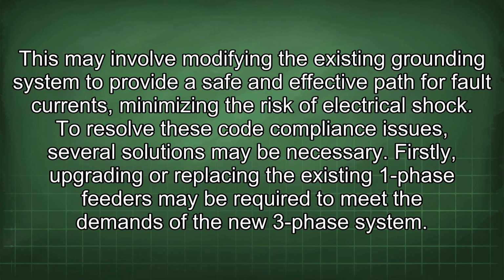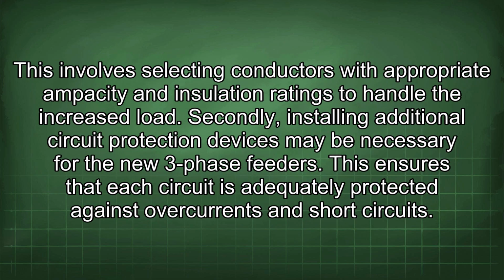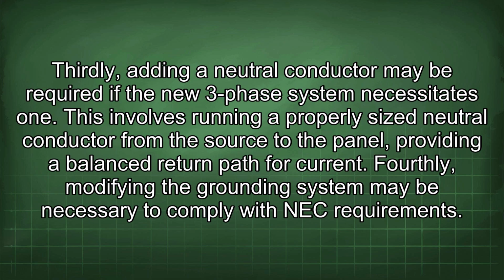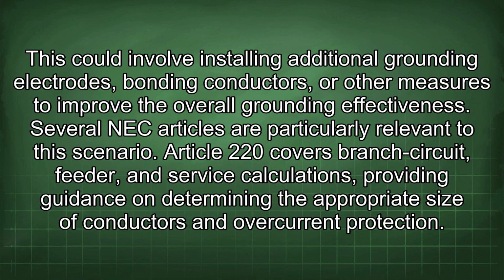Firstly, upgrading or replacing the existing one-phase feeders may be required to meet the demands of the new three-phase system. This involves selecting conductors with appropriate ampacity and insulation ratings to handle the increased load. Secondly, installing additional circuit protection devices may be necessary for the new three-phase feeders. This ensures that each circuit is adequately protected against overcurrents and short circuits. Thirdly, adding a neutral conductor may be required if the new three-phase system necessitates one. This involves running a properly sized neutral conductor from the source to the panel, providing a balanced return path for current. Fourthly, modifying the grounding system may be necessary to comply with NEC requirements. This could involve installing additional grounding electrodes, bonding conductors, or other measures to improve the overall grounding effectiveness.